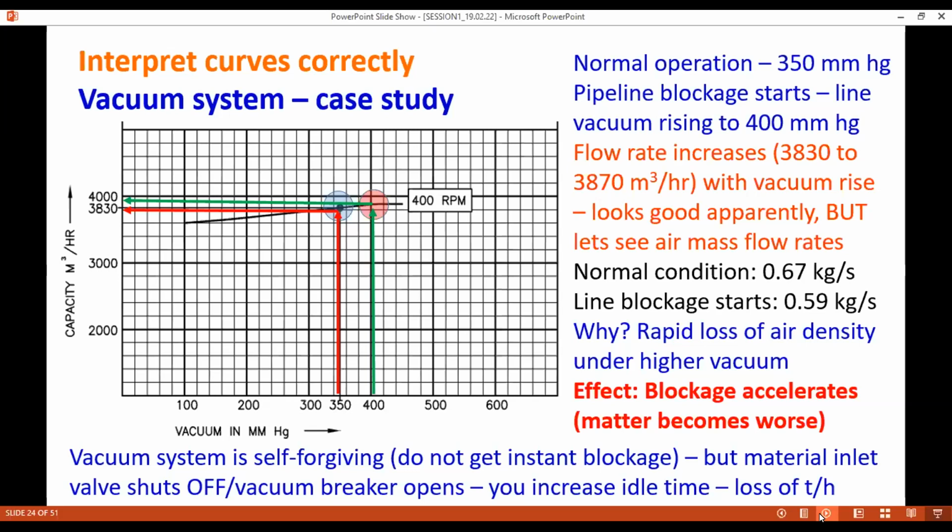In the pressure system, if it blocks and if you have too much fine, then cleaning it can be real hell. Whatever ash we have conveyed, those 40 types of ash, we have seen in the vacuum system, if you stop and start the system, in terms of you stop the material flow, then start it again, after certain trials the system starts to run again. So you might think the vacuum system doesn't choke, which is fantastic.